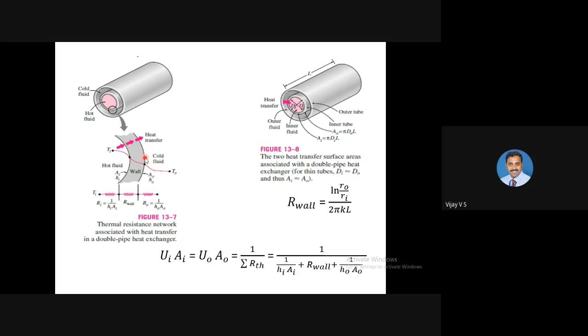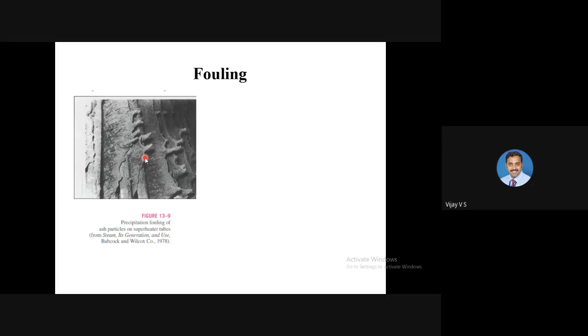Now, how do we calculate this fouling resistance? The resistance offered by fouling is called fouling resistance, and it is calculated based on the fouling factor. See, this is the expression for the fouling factor RF. Generally, when the heat exchanger is very new, they calculate the overall heat transfer coefficient, called U clean. Then after maybe 1 or 2 months of running, they again calculate the overall heat transfer coefficient. The difference between 1 by U dirty and 1 by U clean will be the fouling factor.